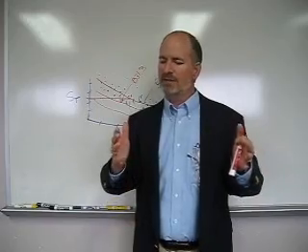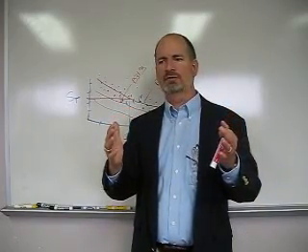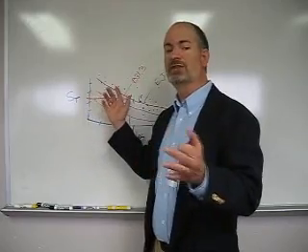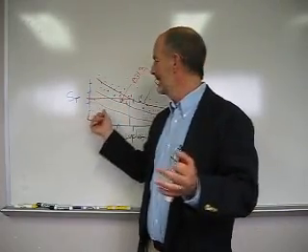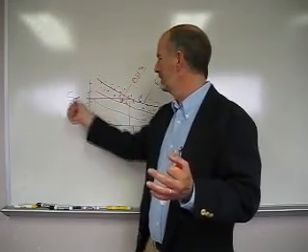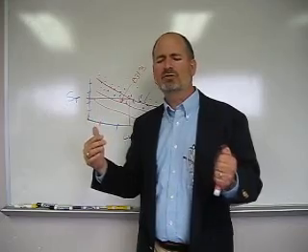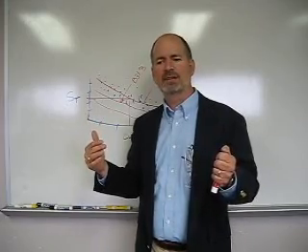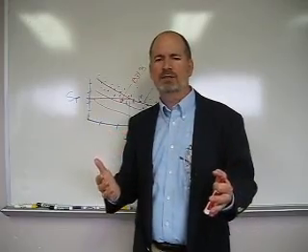Now, to be fair to those guys, they would say you just need to reframe your thinking. Instead of being able to do, say, 7,000 cycles with EJMA, this curve now, this same total stress range, would equate to 200 cycles. So people really shouldn't be specifying 7,000 cycles. They should be more realistic, and they should specify 200 cycles.